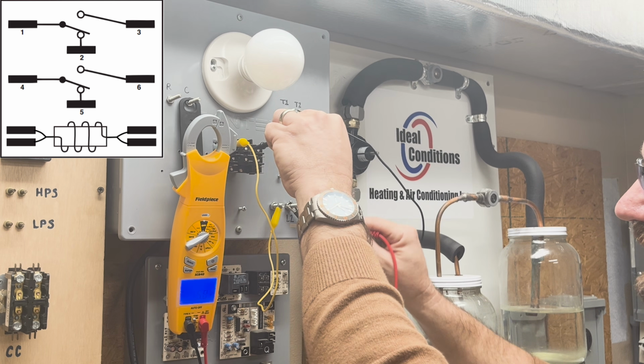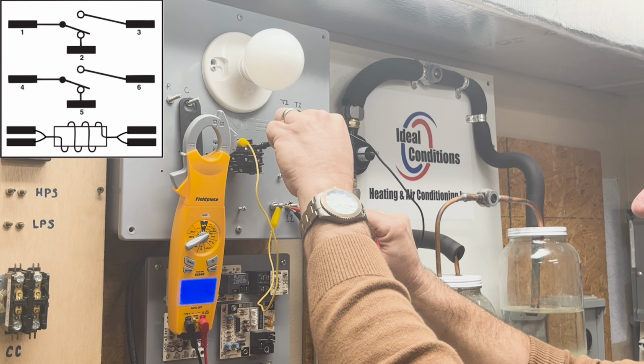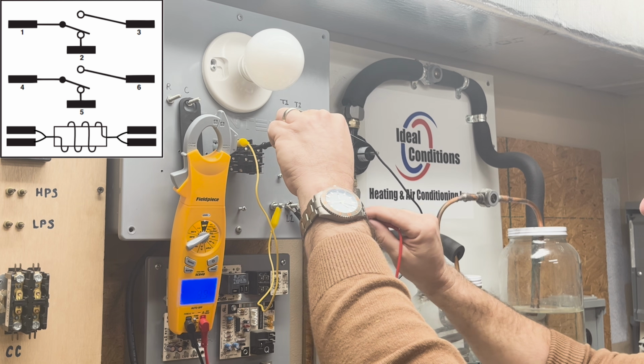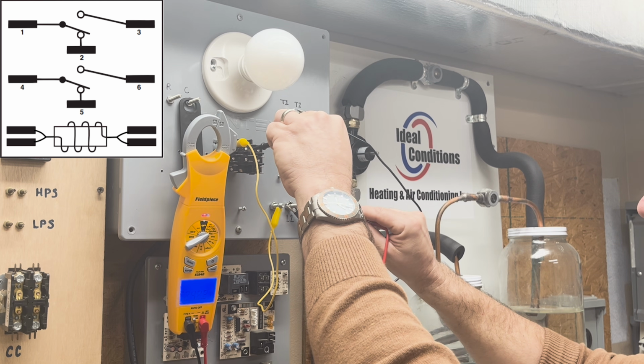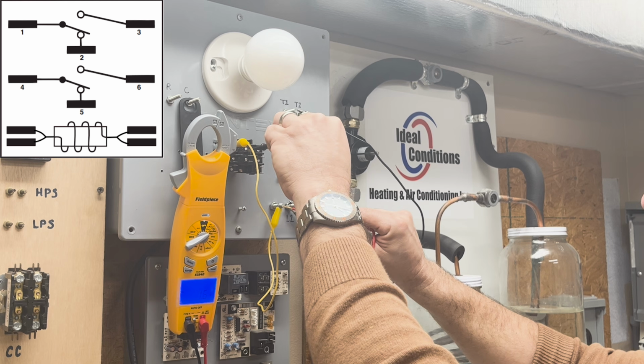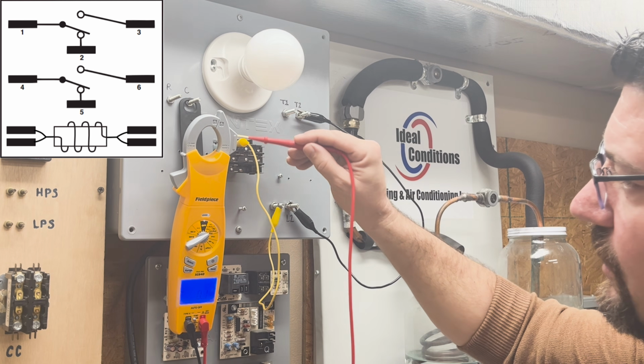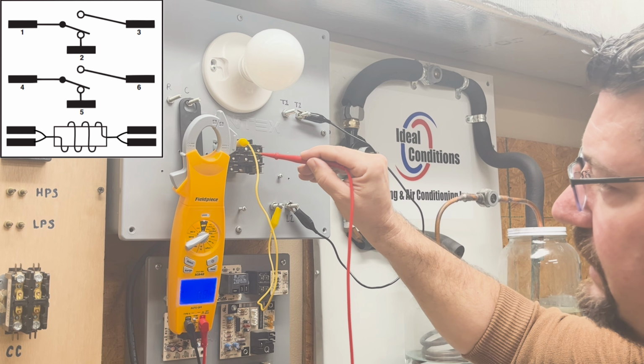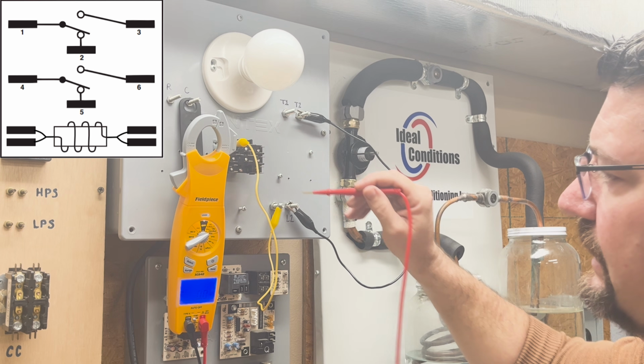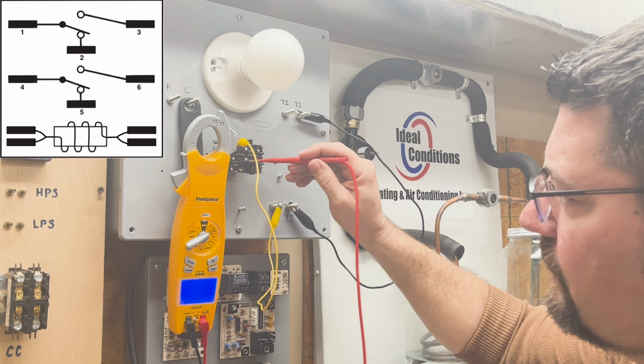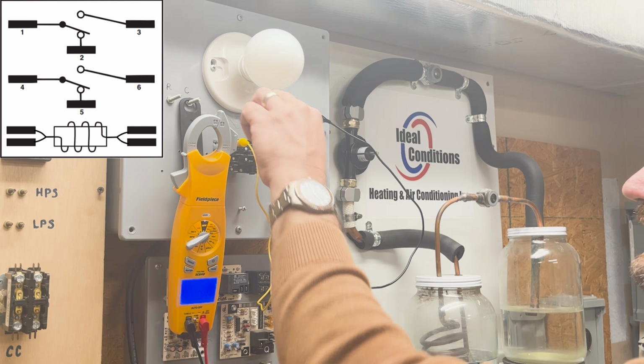I'll demonstrate it down here as well. L1 to 2, 0. 2 to L2, there's 240. Back to L1, there's 0. That's because L1 is present all the way through to the normally closed portion of the relay. Now, there's no power here on 5 or 4 until I give it power.